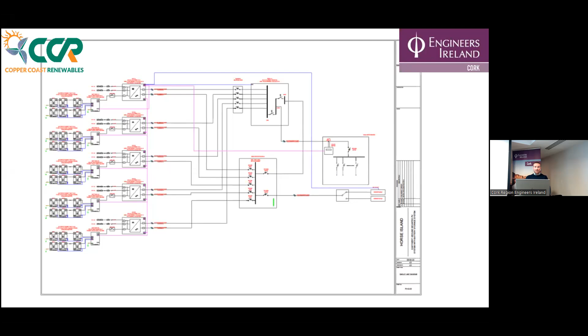On these batteries, we actually had 2 banks of 8 and the rest in 7s. So sometimes we get a voltage difference error, but it's just because we have 1 extra battery running on the inverters. The inverter might show a red LED, but it's still working perfectly, and we can clear it remotely. That's being actioned in a software upgrade with Solax, which is supposed to be rolled out next year.